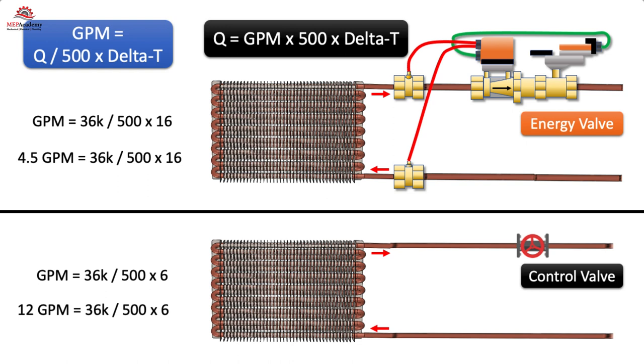If the heat load drops to 36,000 BTUs per hour, which is 30% of the peak design load, then we get 4.5 GPM through the energy valve at a 16 degree delta T. The traditional system is requiring 12 GPM to get the required heat transfer.